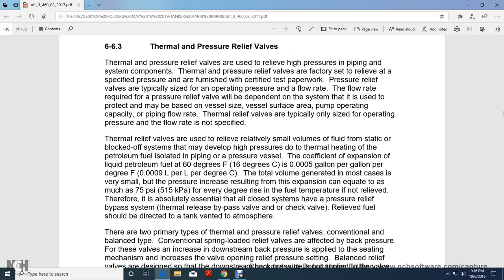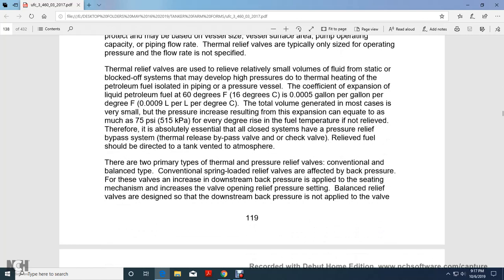Pressure relief valves are typically sized for the operating pressure and flow rate. The flow rate required with the pressure valve is dependent on the system and is used to protect the vessel surface, the pumping operation capacity, and the piping flow rate. The thermal relief valves are typically only sized for the operating pressure; the flow rate is not specified.